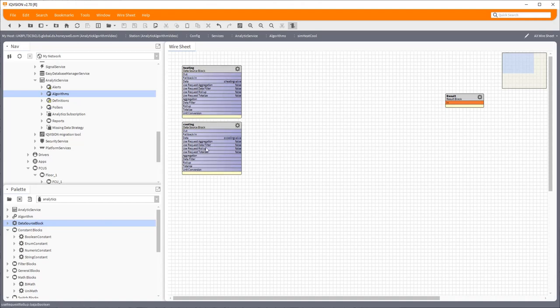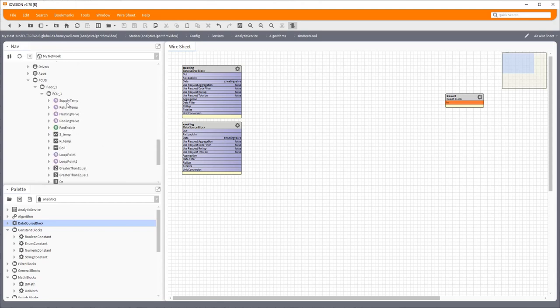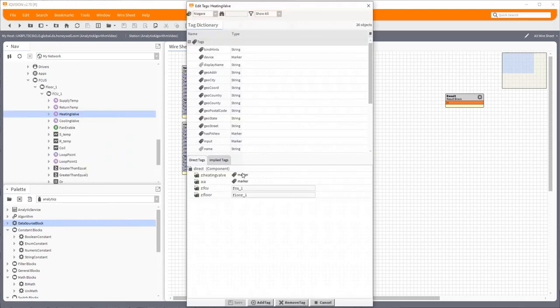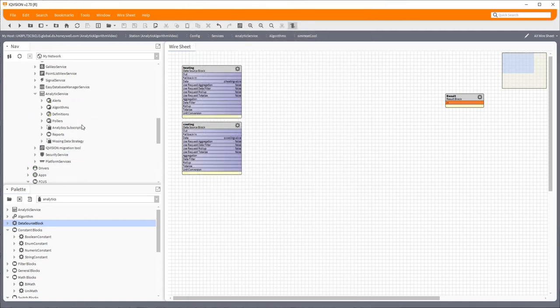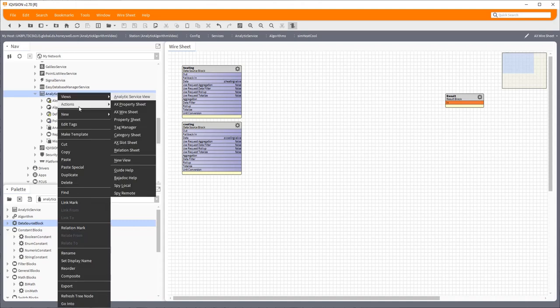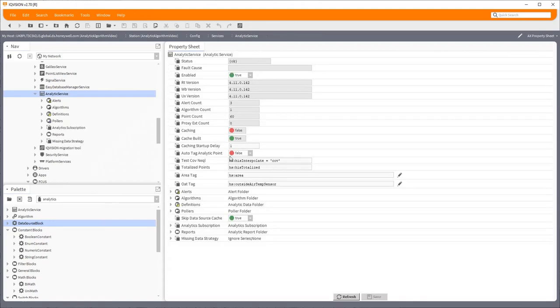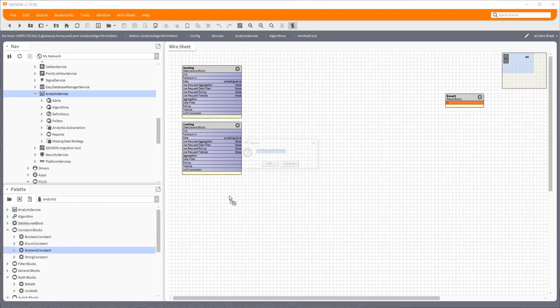Now there is something I should have mentioned earlier perhaps, and that is everything I want to have used in the analytics has another tag in it, a special tag which is this a colon a, analytics. Now you can have the analytics piece put that in for you automatically, and there is a setting in the analytics service. Here, auto tag analytic point. If you set that to true it will add that a:a when it feels it needs to, i.e. if you're picking up something in the analytics engine. I've left mine to false so it doesn't tag everything, so then I can specifically include or exclude things from my analytics algorithms. It's up to you which one you actually do.